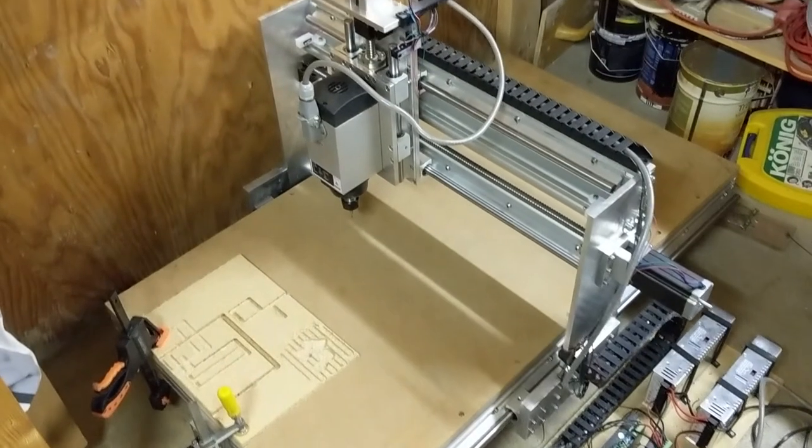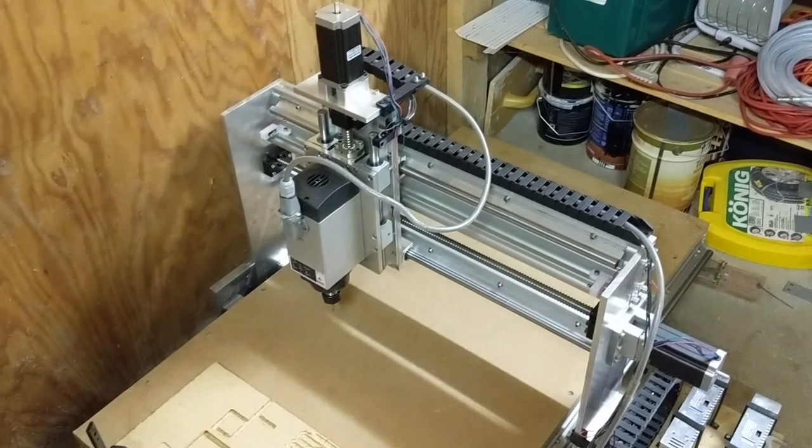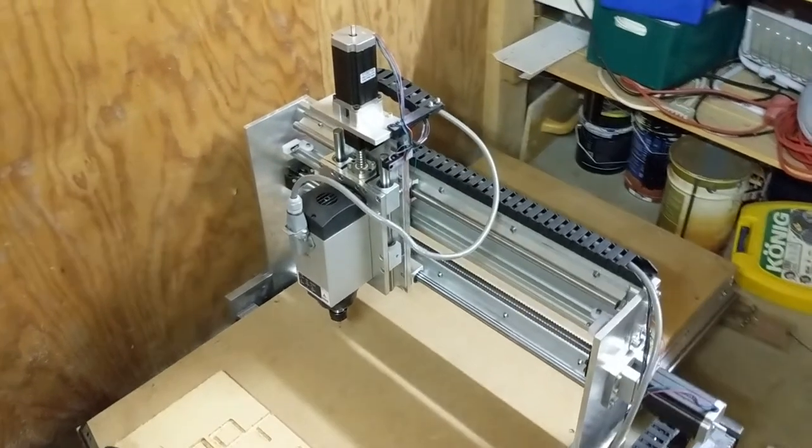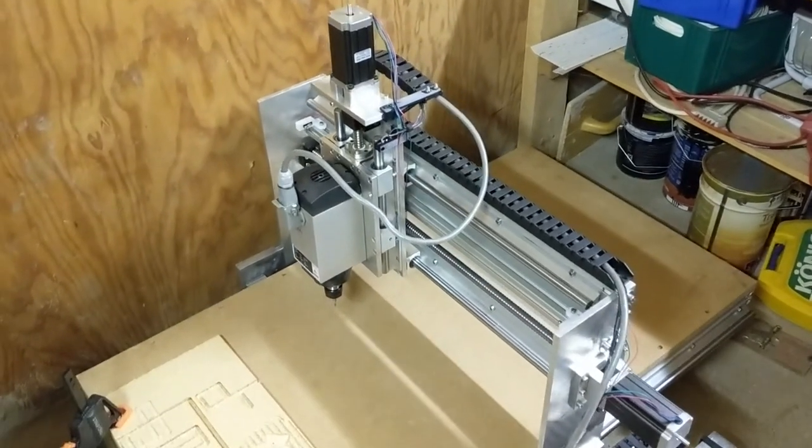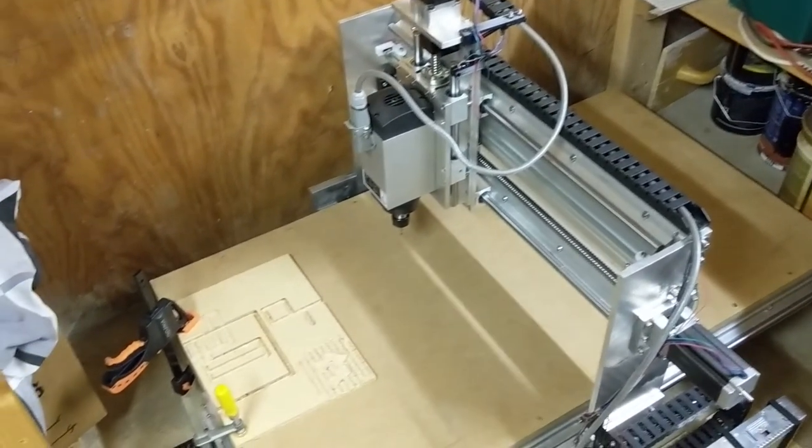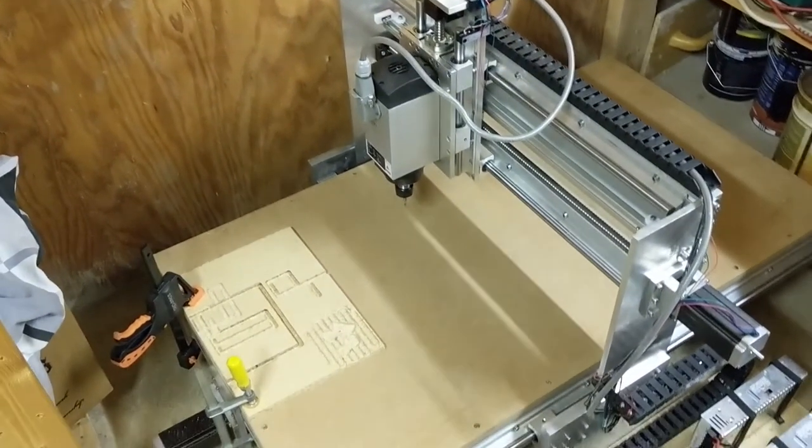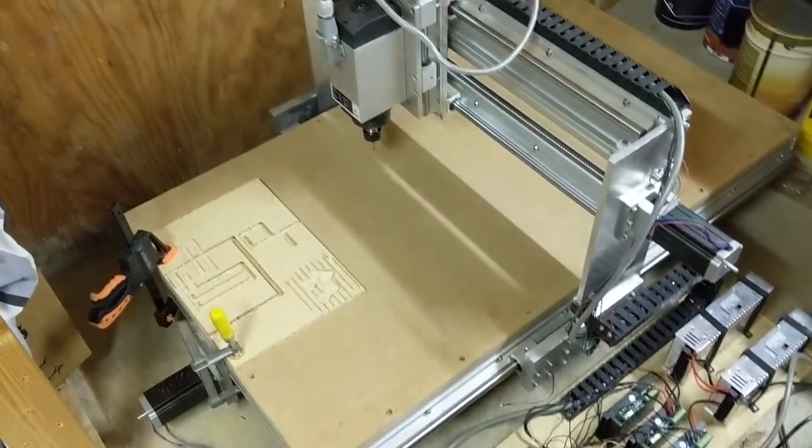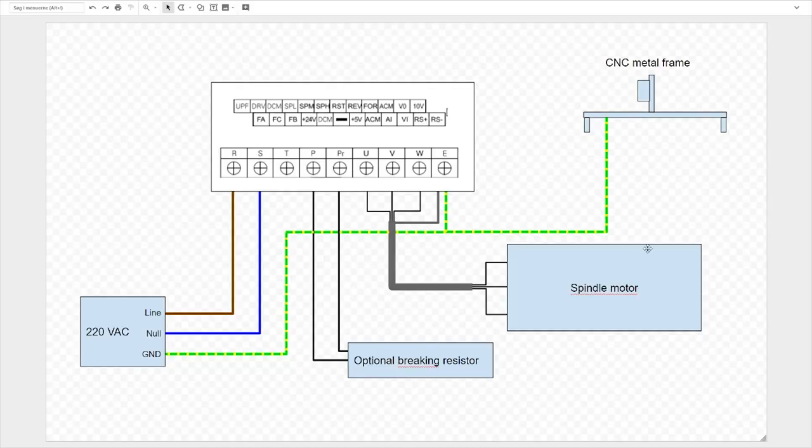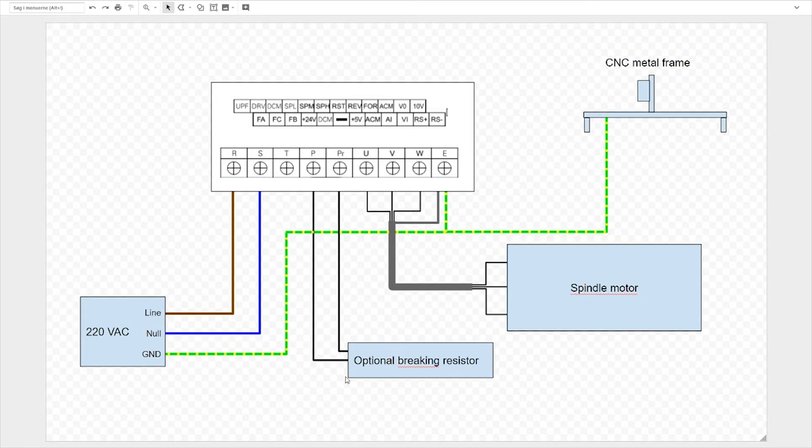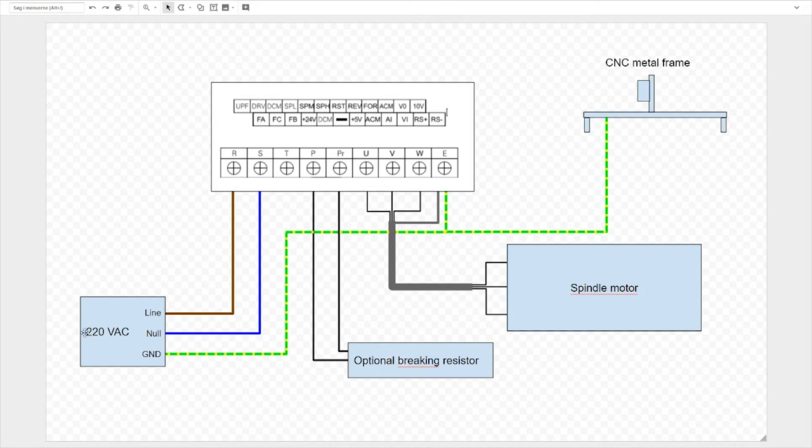Now I will show you a diagram of how I've connected everything together. You can also find a link to a very detailed manual for all Huanyang VFDs in the description. So this shows how all the power wires should be connected together. This is the input on the Huanyang, this is your metal frame on the CNC, your spindle motor, an optional braking resistor and your 220 volts input. This could also be 120 volts if that's what you have or 400 volts. So this is connected in a bit different ways depending on your VFD. Please look in the manual.